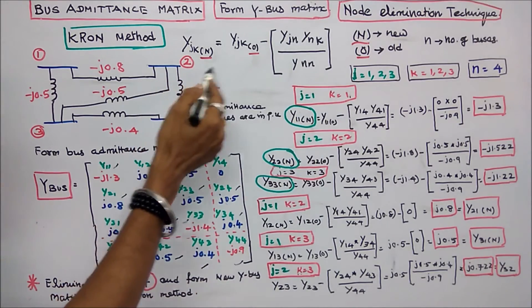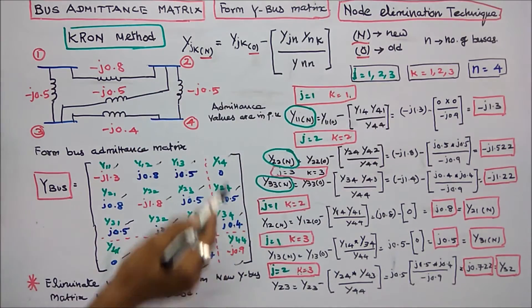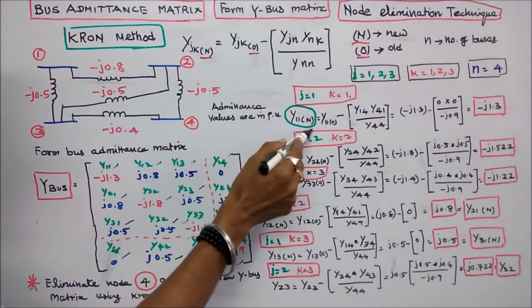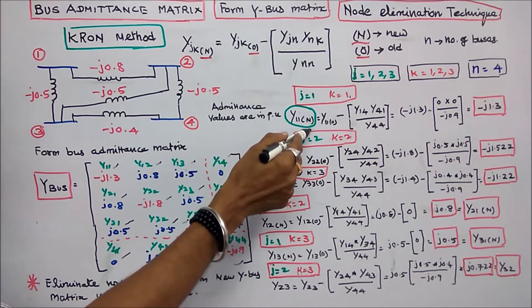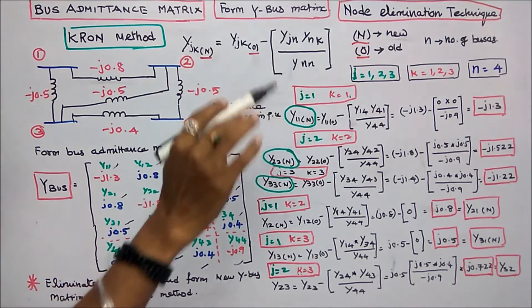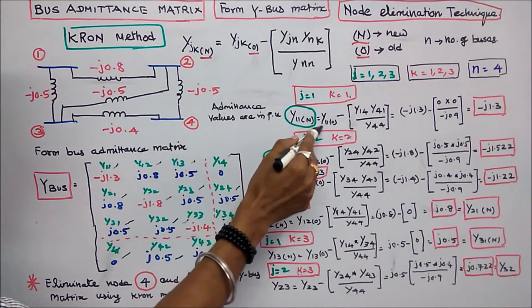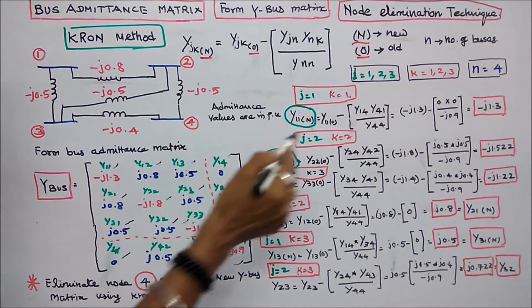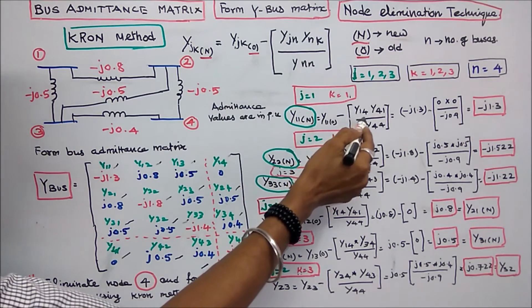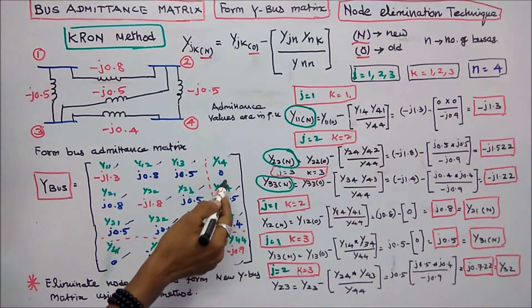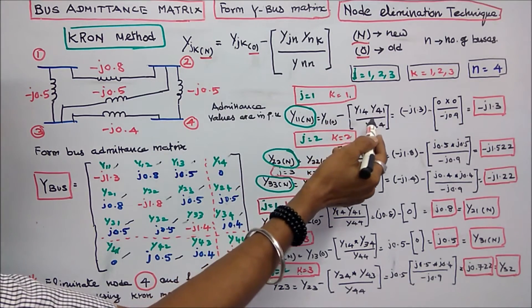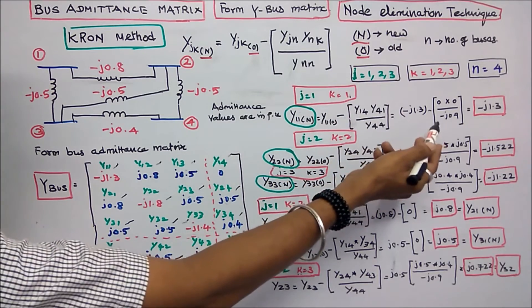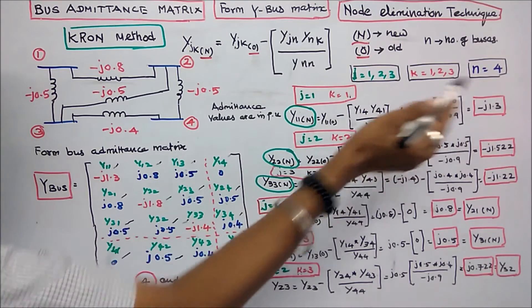Where N is the node being eliminated, J and K each range from 1 to 3. Applying the formula for Y11 new: Y11(new) = Y11(old) minus Y14 times Y41 divided by Y44. Y11(old) is minus j1.3, and since Y14 equals 0 and Y41 equals 0, the result is minus j1.3.